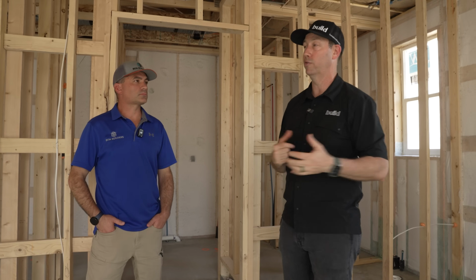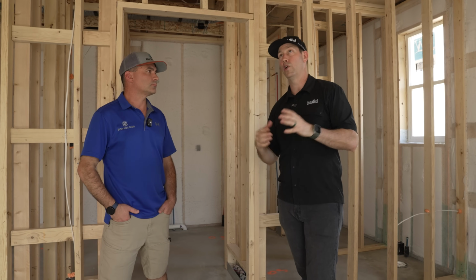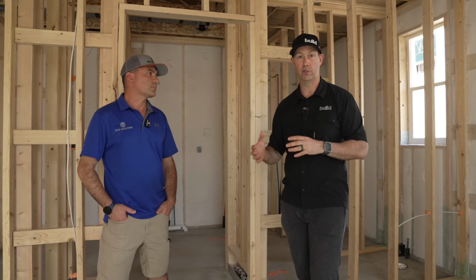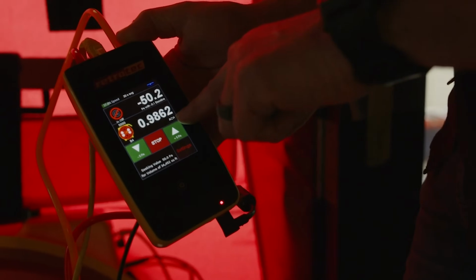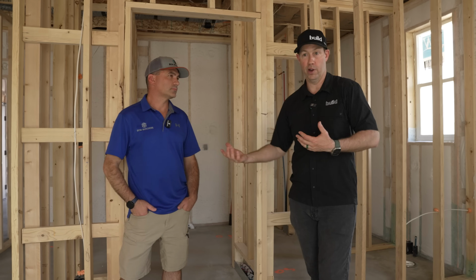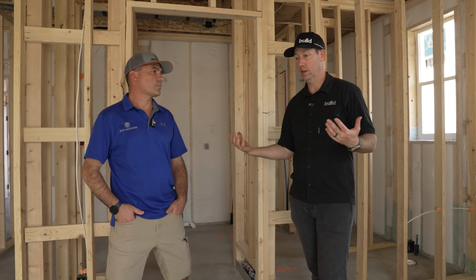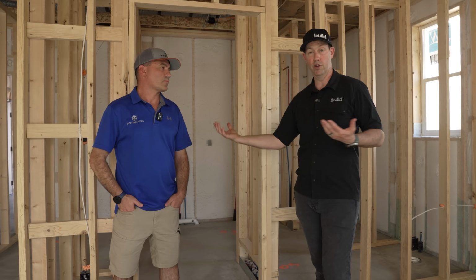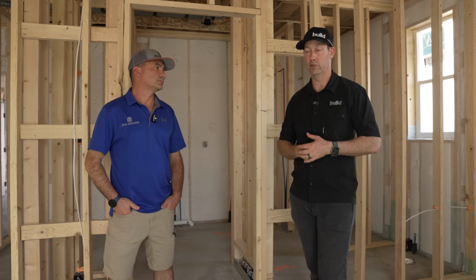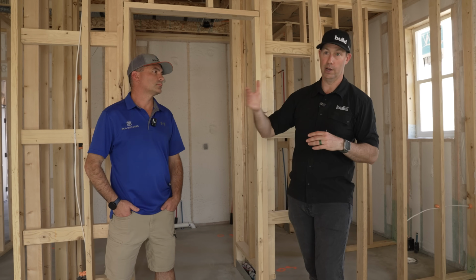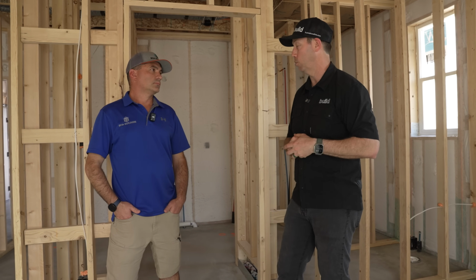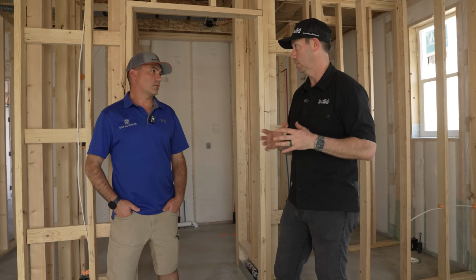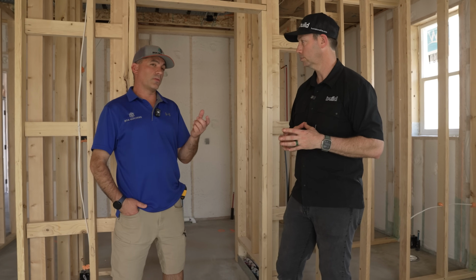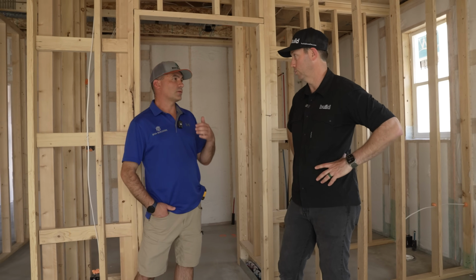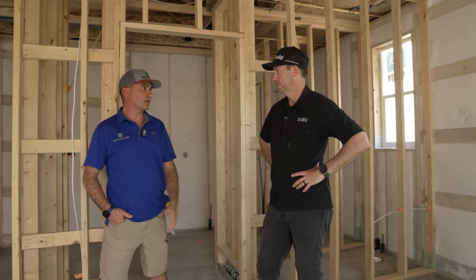At my house, I went from about 1.1 ACH50 down to like 0.1 ACH50. But it works well for any size house or any leakiness. Even a 4 ACH house, which would have been code approved and still is in Texas, you can get down quite low to around 0.8. And that ACH number really helps the load on your HVAC equipment, since a lot of that leakage factors in.